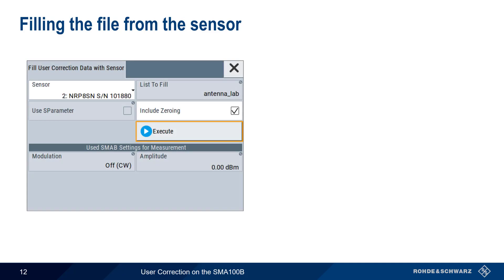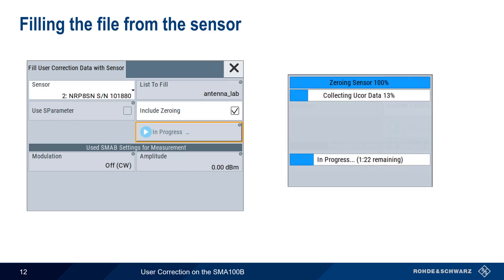To fill the user correction file from a sensor, we first choose the sensor we want to use, and whether or not we want the sensor zeroed before calculating the corrections. After pressing Execute, the data collection process begins, and usually takes several minutes, depending on the number of steps. When the process is completed, we can return to the main User Correction screen.